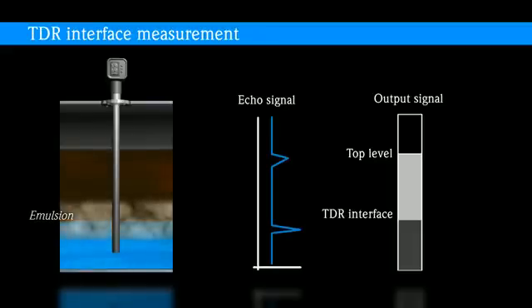If an emulsion layer frequently forms between both media, this might damp the measured value and even cause a complete loss of the interface signal. This means that the interpretation of the interface signal coincides with the overall level signal. The interface layer is thus not safely detected under emulsion conditions and optimum process control cannot be guaranteed.